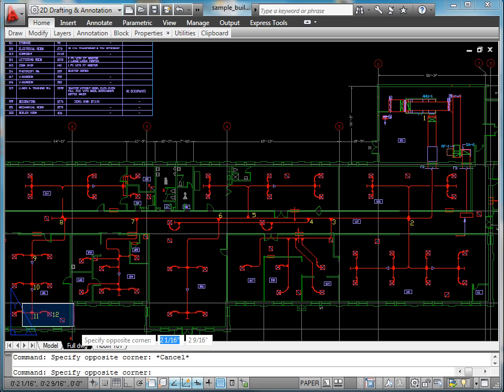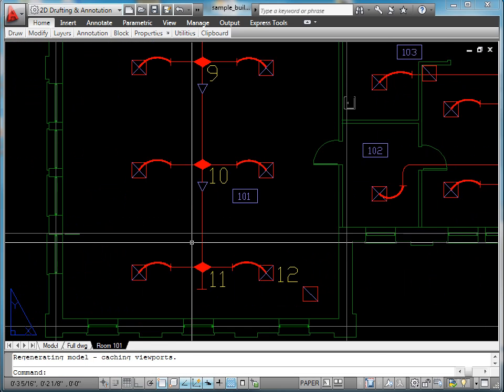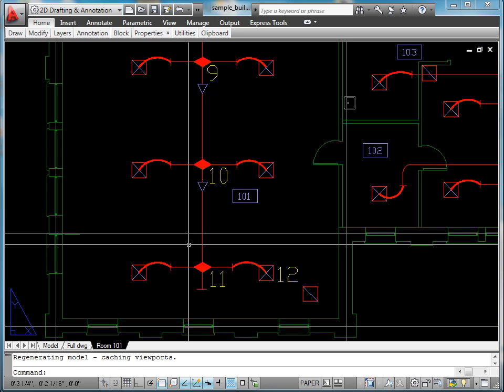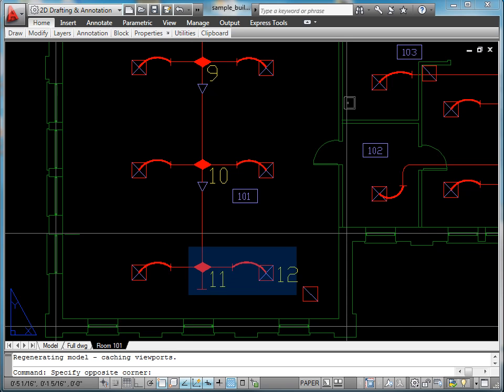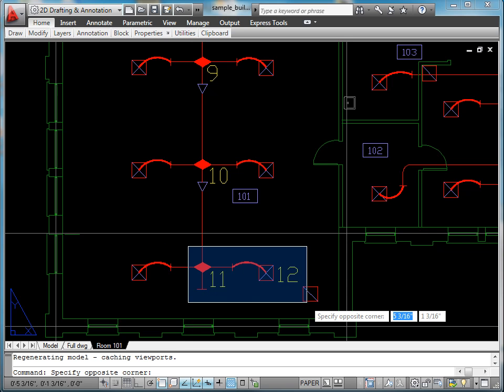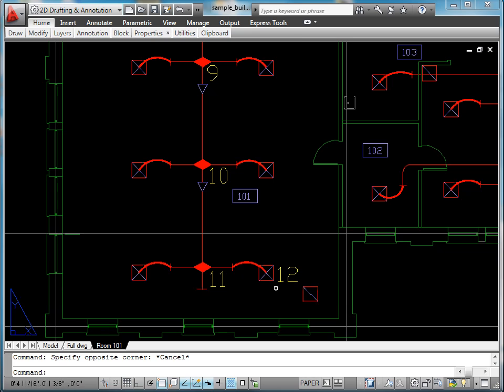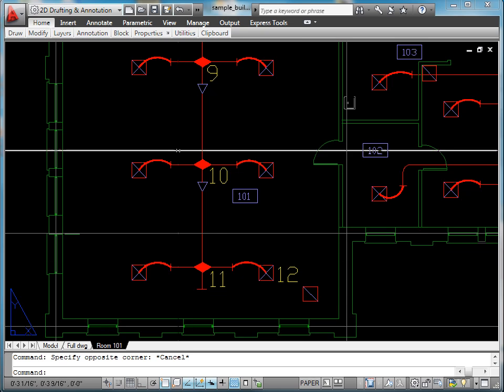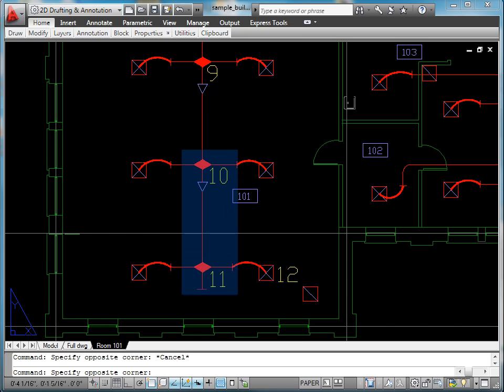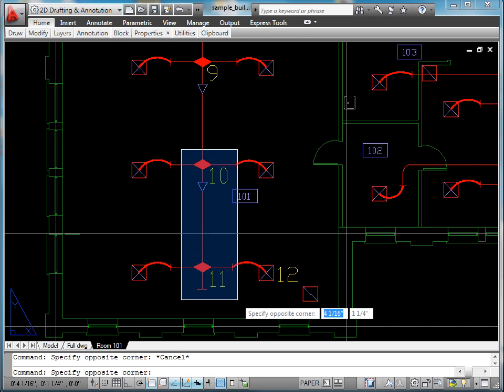The next step is to calculate the airflow rates for each of the marked sections. For example, the airflow rate for section 11-12 equals the airflow rate through one diffuser. Section 10-11 carries air for two diffusers. Therefore, the airflow rate for this section is double the rate of section 11-12.